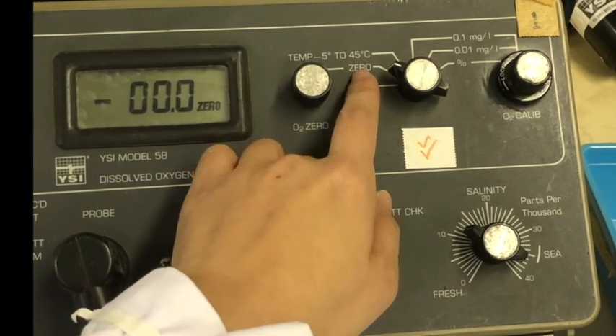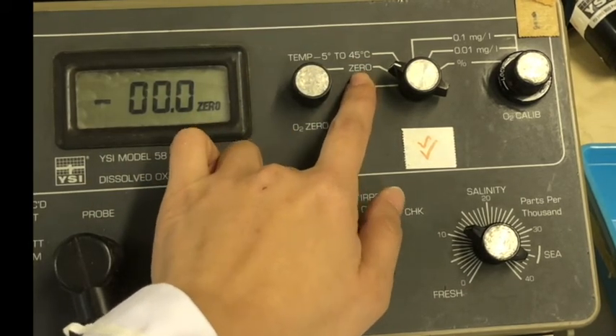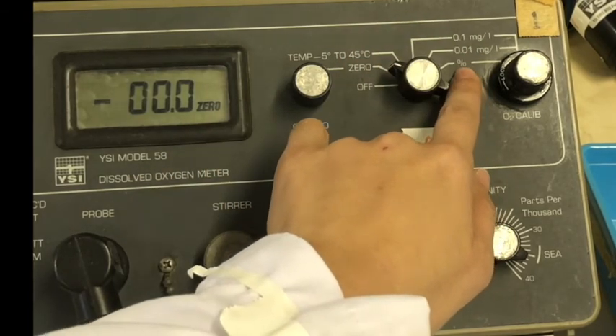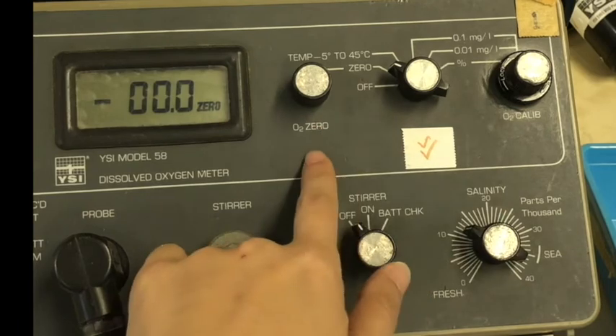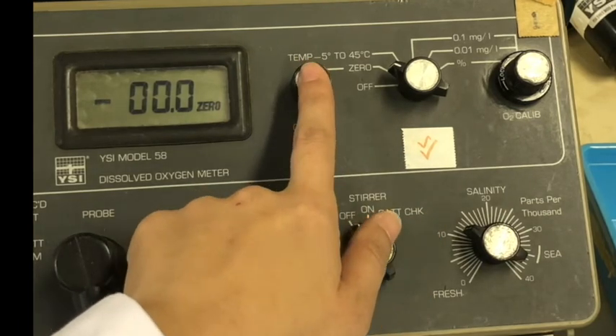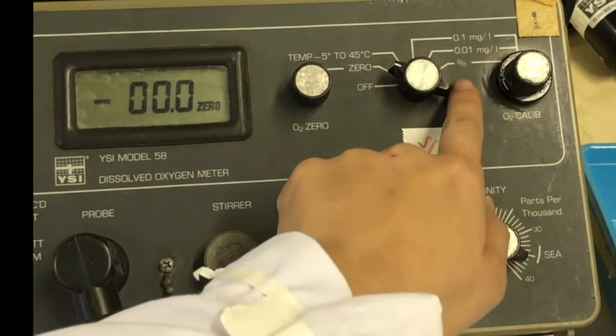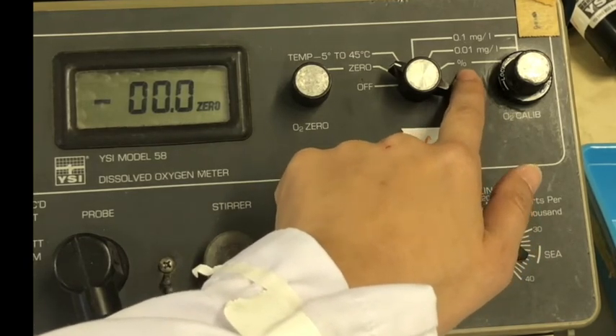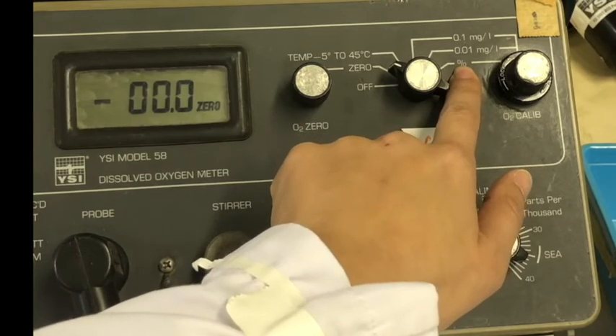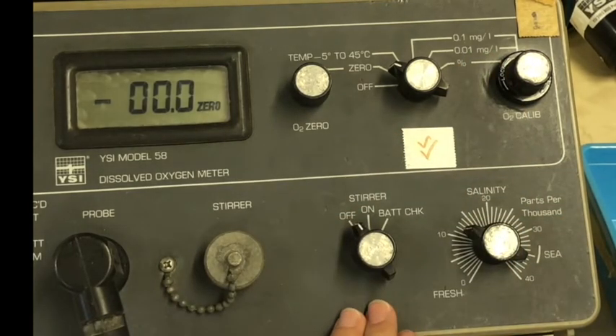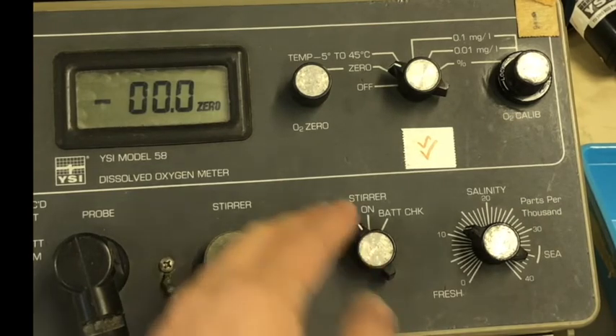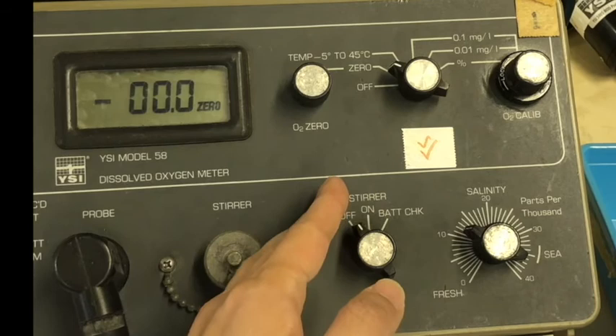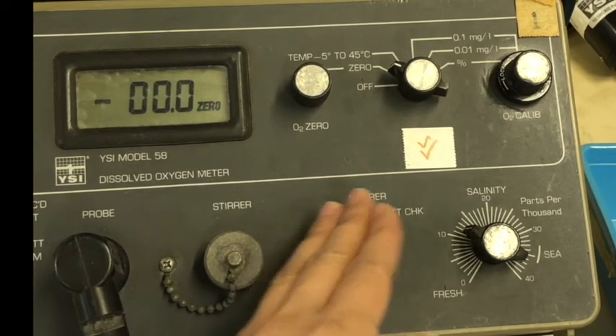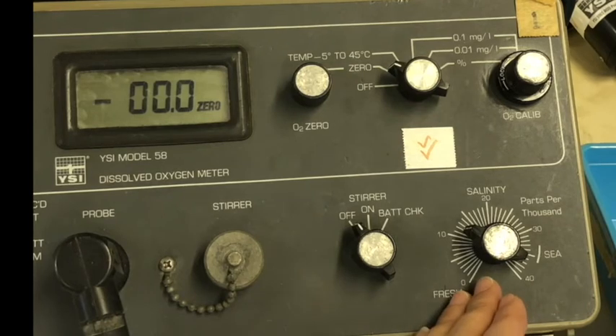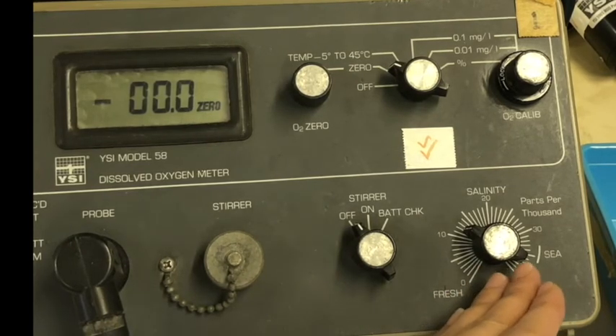For the calibration procedure, we need to set 0 without any water sample, and then switch to the percentage for saturation. For setting 0, just adjust this button. After setting 0, switch to the percentage for saturation. During the measurement, we need to stir the water sample by turning on the stirrer. For either measurement or the calibration, we need to adjust the salinity. For the calibration process, the salinity should be 0.